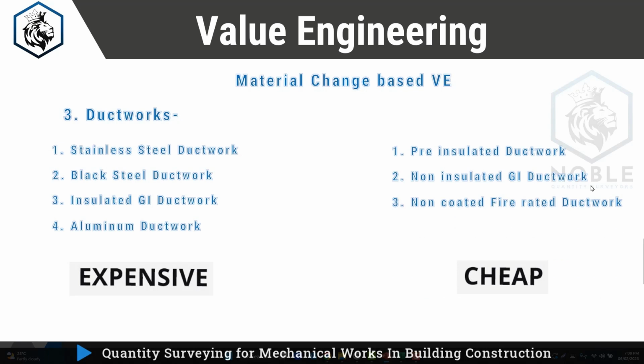The next is non-coated fire-rated ductwork. Fire ductwork is of two types: coated and non-coated. You need to check thoroughly in the specification what they have mentioned. If it is coated fire-rated ductwork, you can propose non-coated fire-rated ductwork instead. Coated fire ductwork costs around 150 dirhams per square meter, and non-coated costs around 90 dirhams per square meter. So there's almost 30 to 35% cost savings.